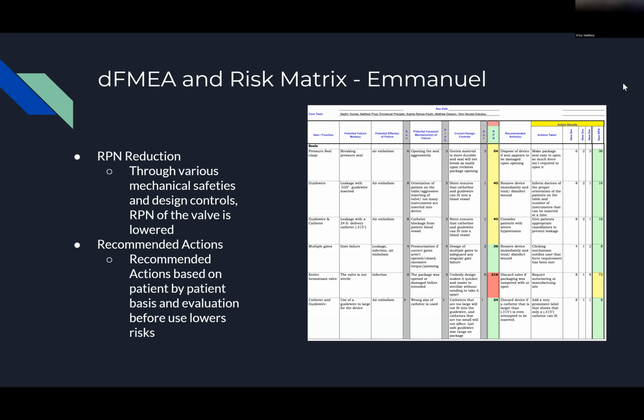This is the design failure mode and effects analysis for a hemostasis valve. The DFMEA is used to determine risks involved in a medical design using the severity and probability of an effective failure. Based on our choices for our design, we have identified failure points in current hemostasis valves on the market. As for the medical use of these devices, it's very important. We have design controls in place to reduce risk using our valve.